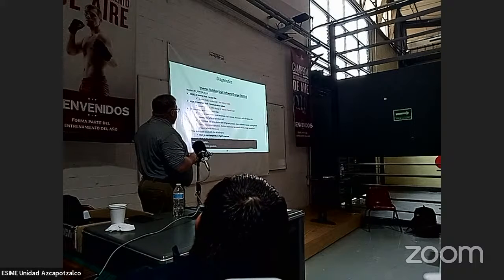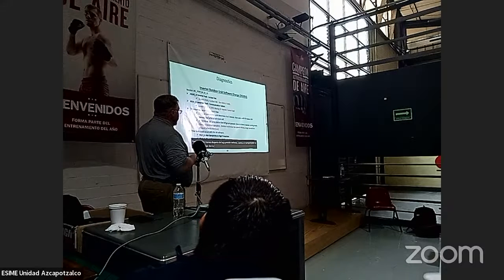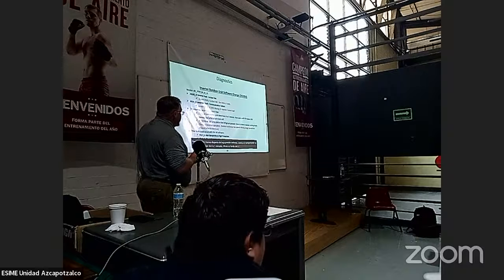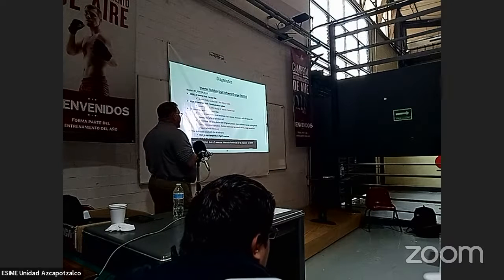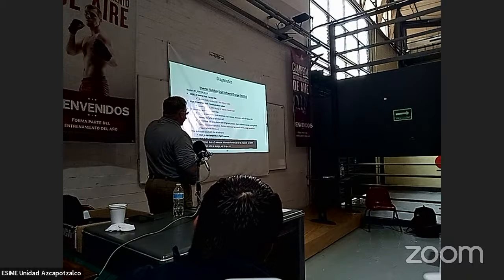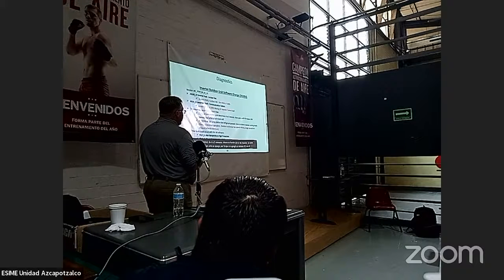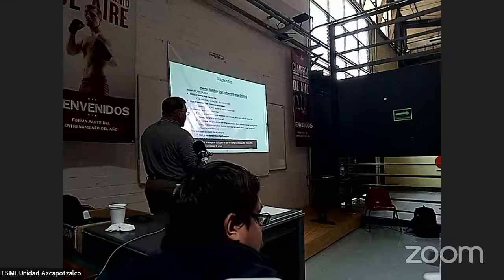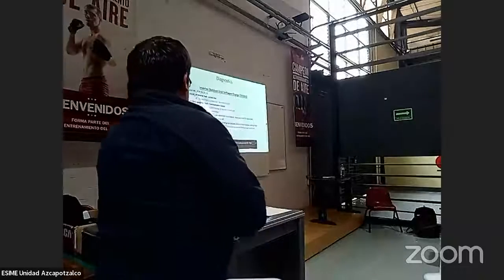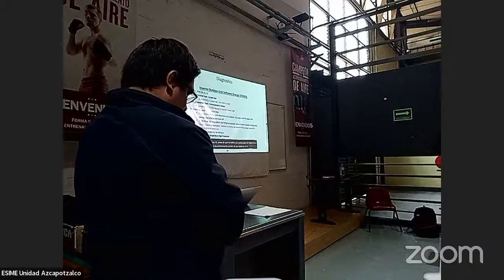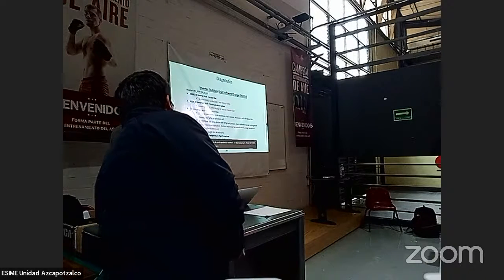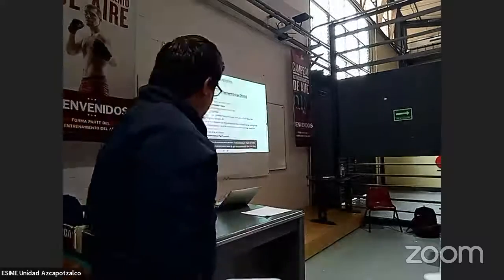To reduce nuisance low pressure trips, change the compressor cycle time from 4 to 5 minutes. Now it syncs with the indoor EXV. Opened after a cycle turns off. So we added a 90-second delay for low refrigerant pressure changes done in normal cooling mode. That way, if it's a little cooler and our pressures drop before they come back up, there's a 90-second delay before we'll kick off on the pressure.